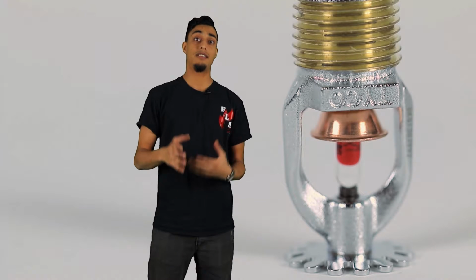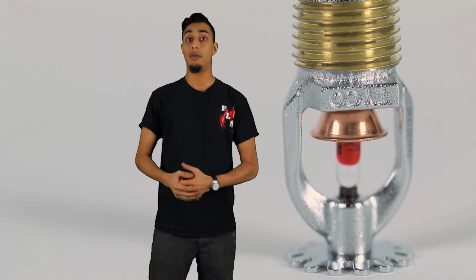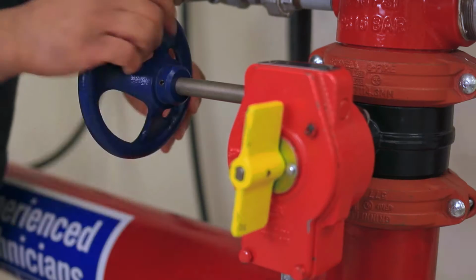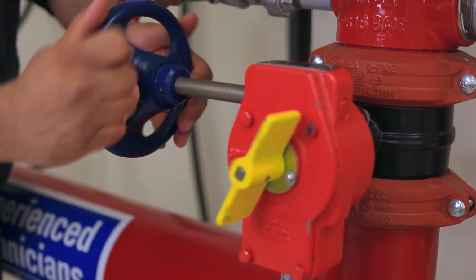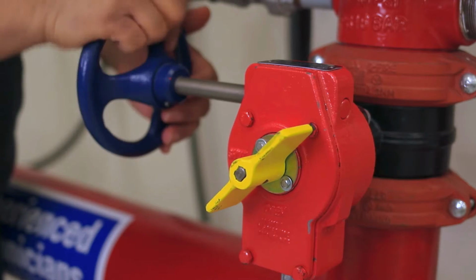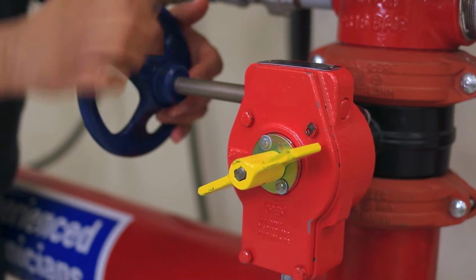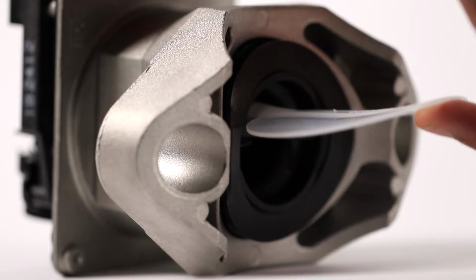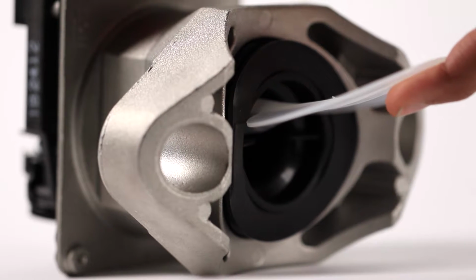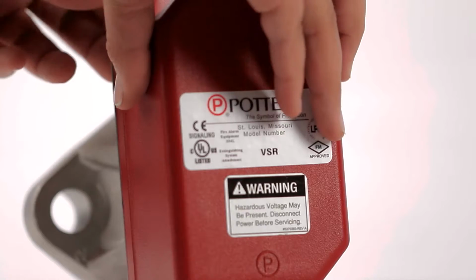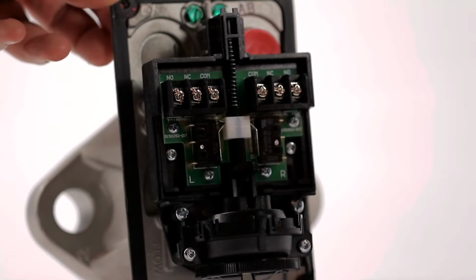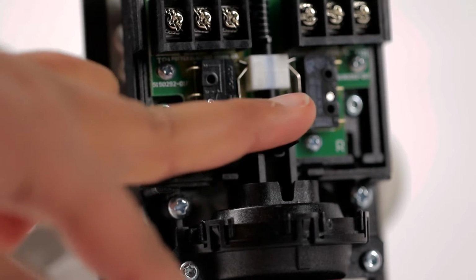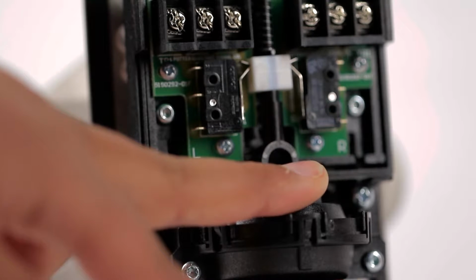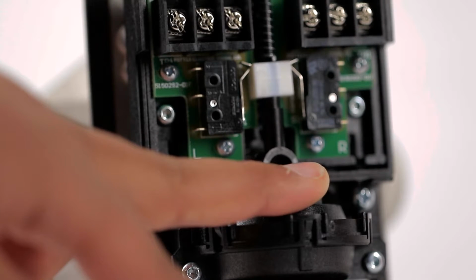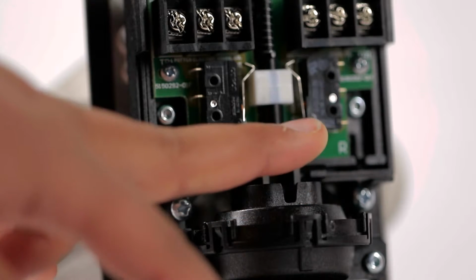When testing sprinkler systems, NFPA 25 is a standard created by a third-party company brought into legislation by the Fire Code. In this standard, it is explicitly defined the proper procedures necessary for testing our sprinkler system, which includes flowing water to gain a proper understanding of how our system will function in the event of an emergency, as opposed to removing the case off the back of our flow switch and simply short-circuiting the electrical connections or physically moving the lever. These would be incorrect or improper examples of testing.